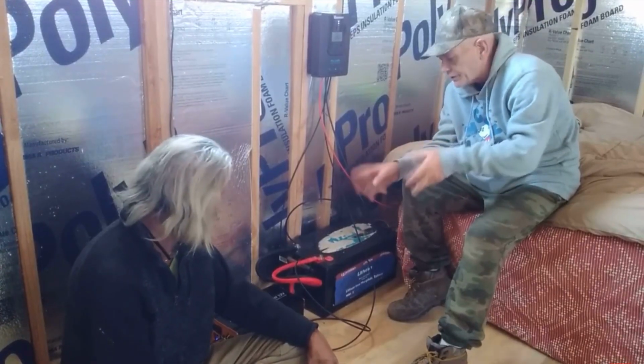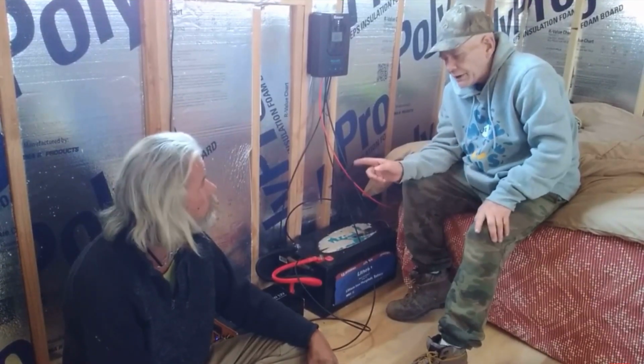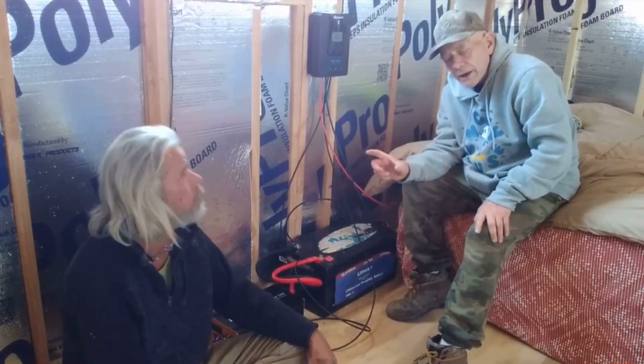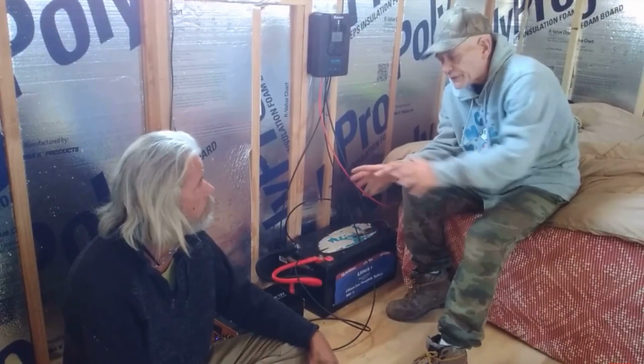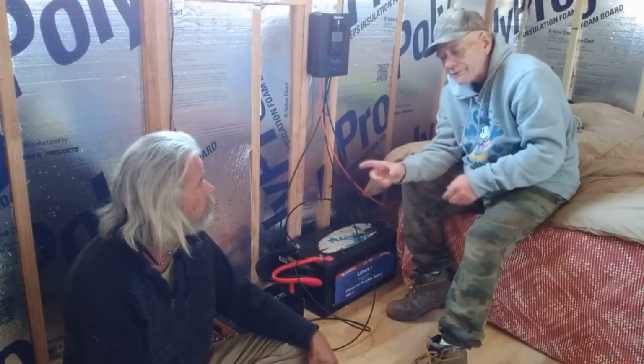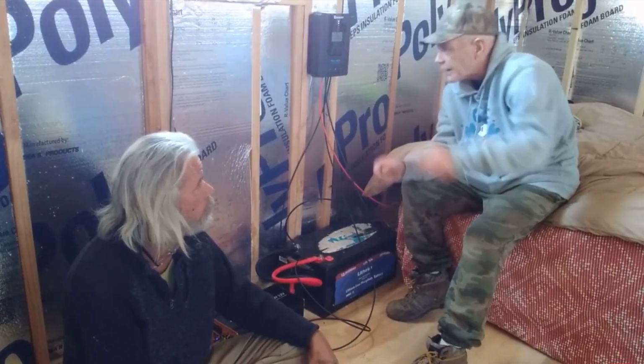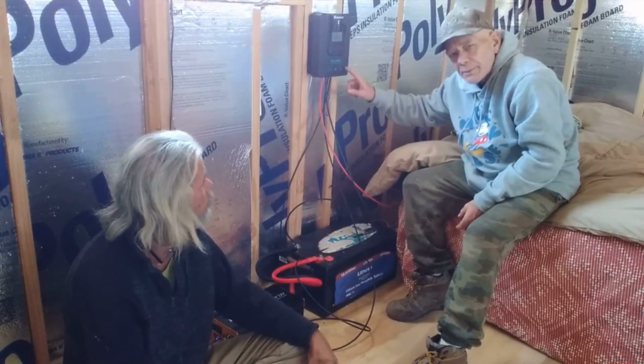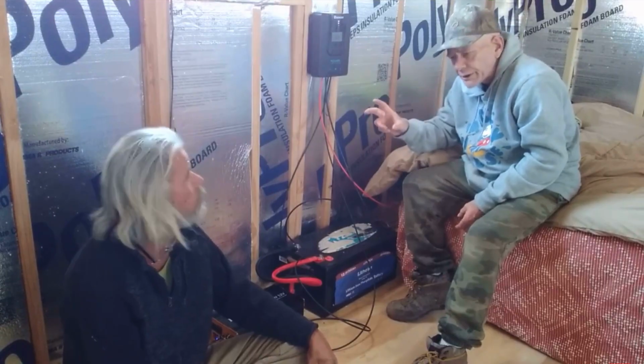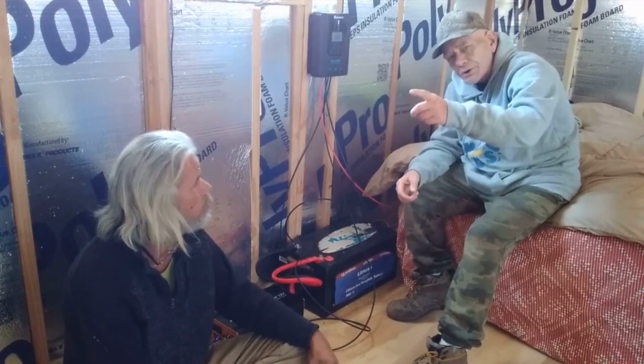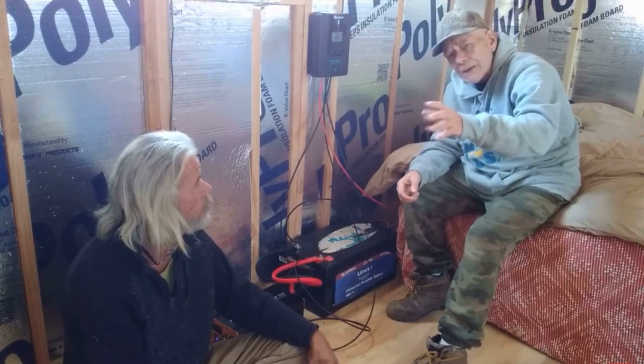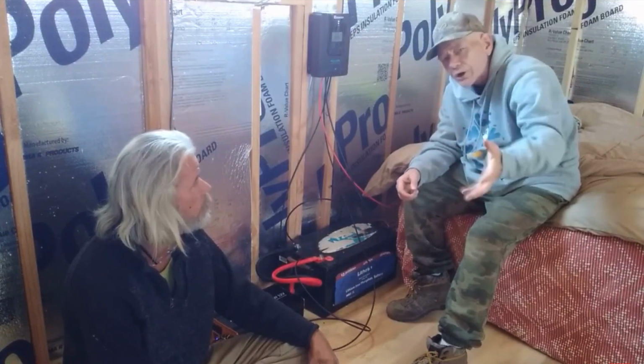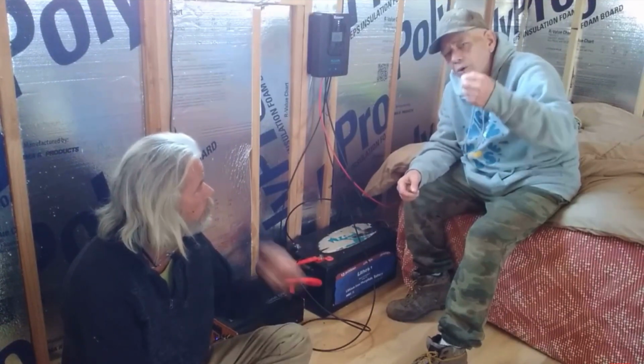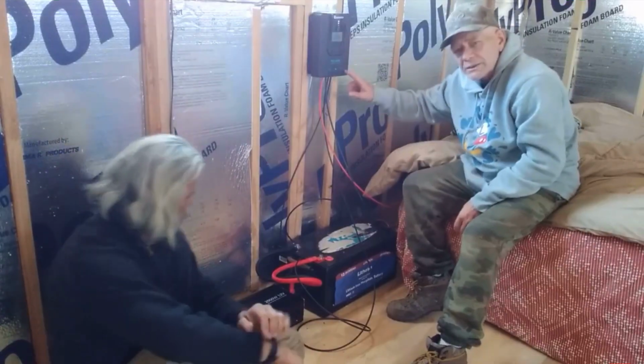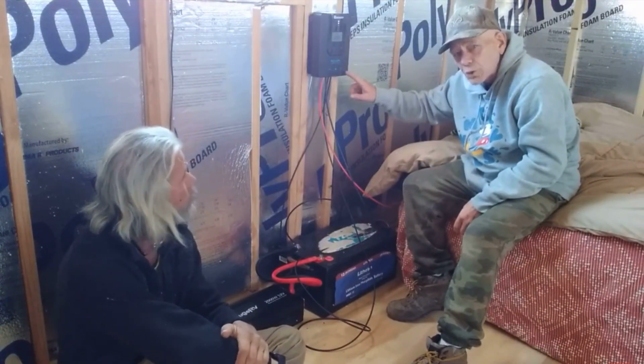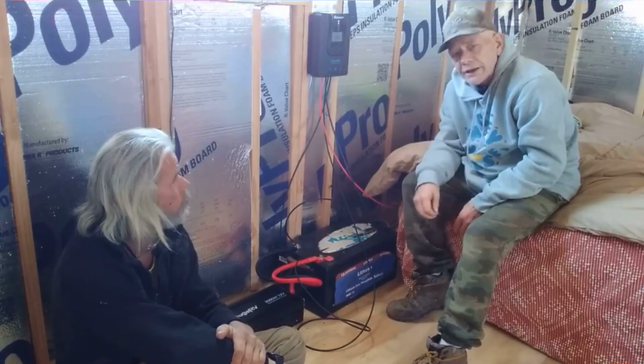The only thing I didn't include is he needs to get a fuse link. A fuse link is just a safety feature. This is fine for now, but a fuse link will go between the solar panels and the controller, and I recommend probably a 30 amp fuse link, going in the connection between the solar panels. That way, if something happens like a lightning strike or a short in the solar panels, it will blow that fuse instead of possibly damaging your controller. So that's the one thing to add, and he will order that and get it put in.